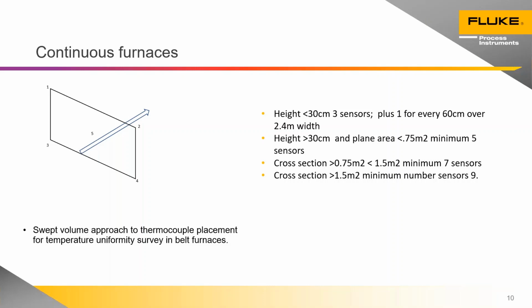On the right-hand side of the screen, you see there's some recommendations in terms of the number of sensors required relating to the height of the furnace. So less than 30 centimeters height, only 3 sensors are required, unless the belt width is more than 2.4 meters, then you start adding extra sensors. For furnaces above 30 centimeters, then you need to measure both top and bottom on the left and right. And the sensors up in the top corners have to be within 75 millimeters of the work volume.